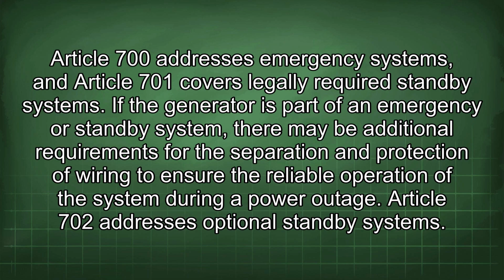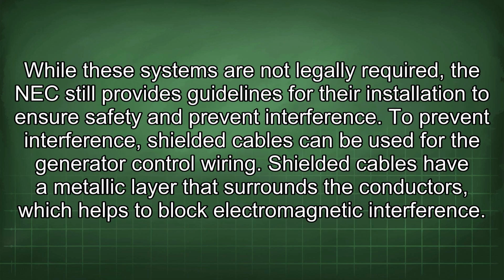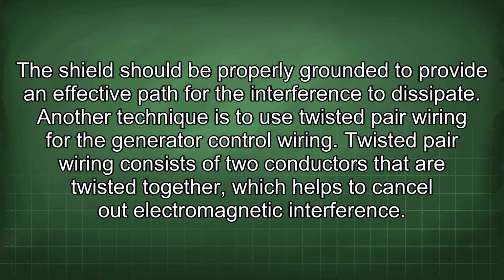Article 702 addresses optional standby systems. While these systems are not legally required, the NEC still provides guidelines for their installation to ensure safety and prevent interference. To prevent interference, shielded cables can be used for the generator control wiring. Shielded cables have a metallic layer that surrounds the conductors, which helps to block electromagnetic interference. The shield should be properly grounded to provide an effective path for the interference to dissipate.